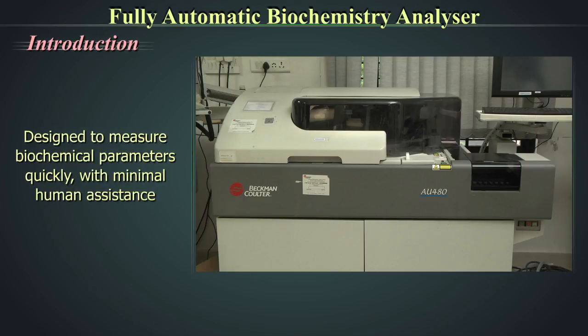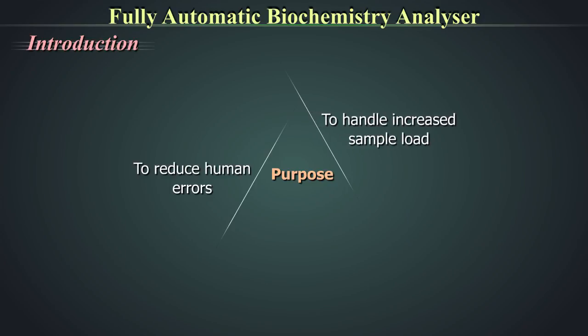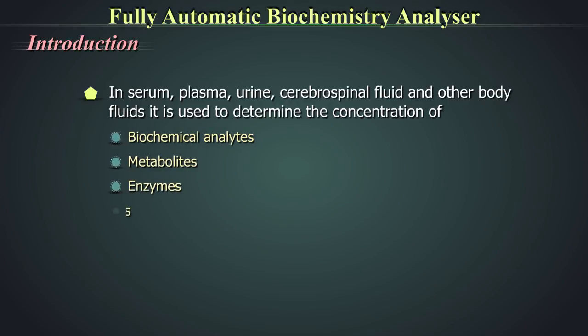A fully automated biochemistry analyzer is designed to measure biochemical parameters quickly with minimal human assistance. The purpose of this analyzer is to reduce human errors, handle increased sample load, and provide accurate results more efficiently. They are used to determine the concentration of various biochemical analytes, metabolites, enzymes, electrolytes, drug levels, etc.